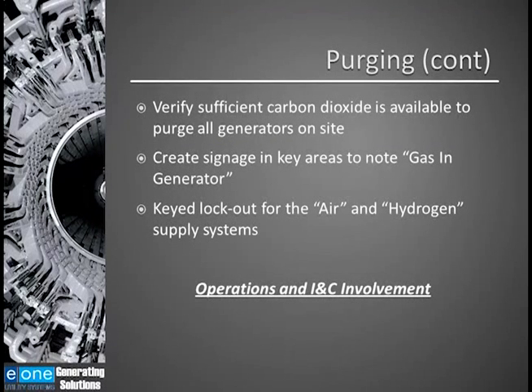You also want to make sure that you have a sufficient amount of carbon dioxide available, not only to purge the generator that you're working on, but also to purge all the generators that are on site. Because emergencies can occur where you want to purge those generators, and you want to make sure that you have a sufficient amount of carbon dioxide to purge them.